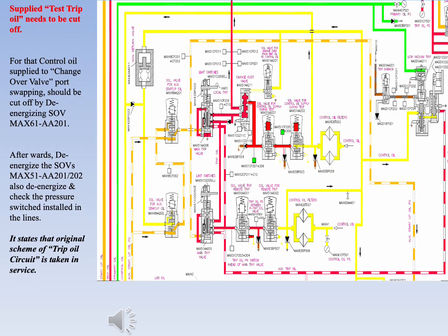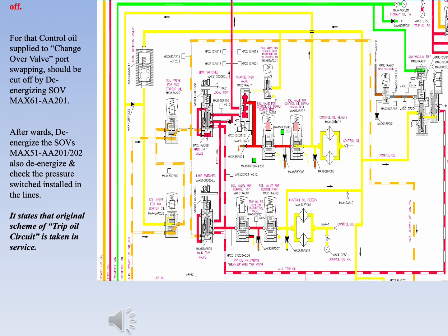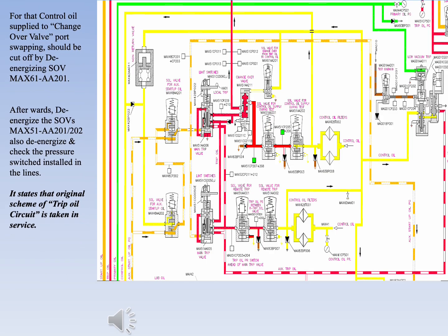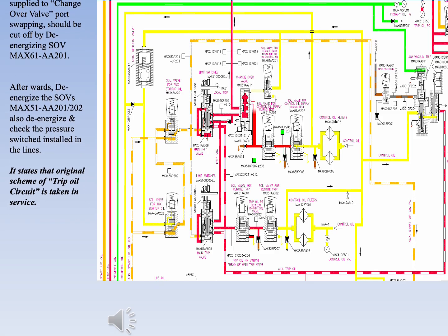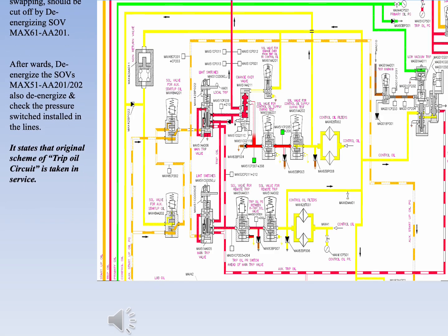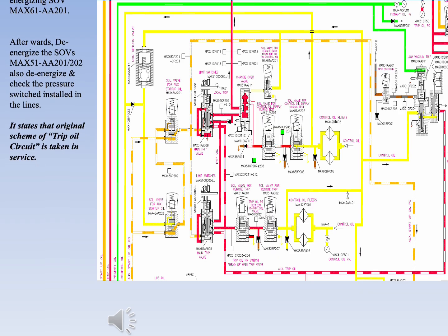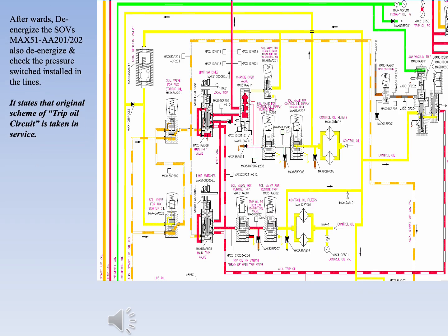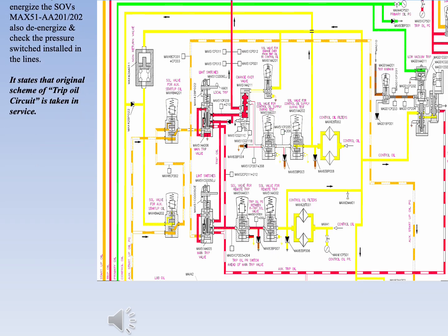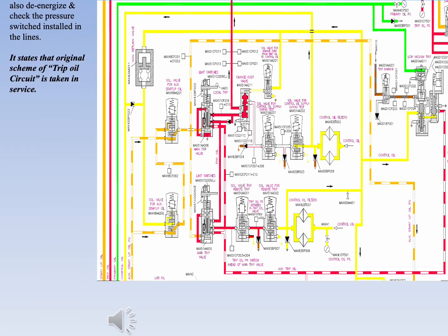Afterwards, de-energize the SOVs MAX51 AA201/202. Also, check the pressure switch status installed in the lines. It states that the original scheme of the trip oil circuit is taken into service.